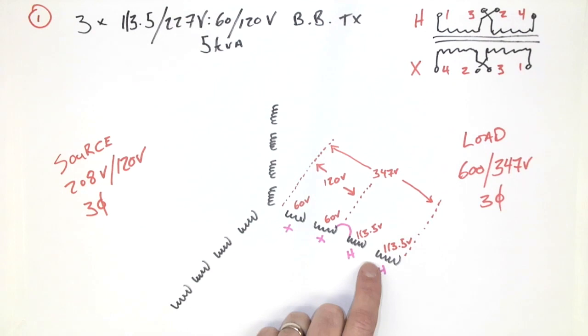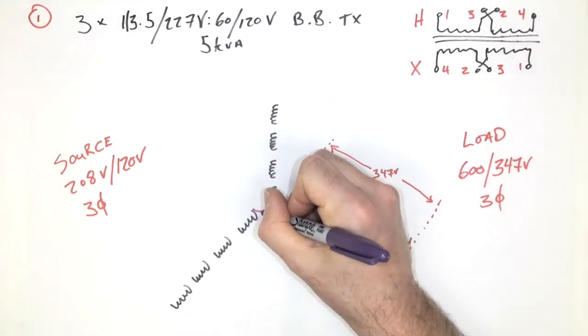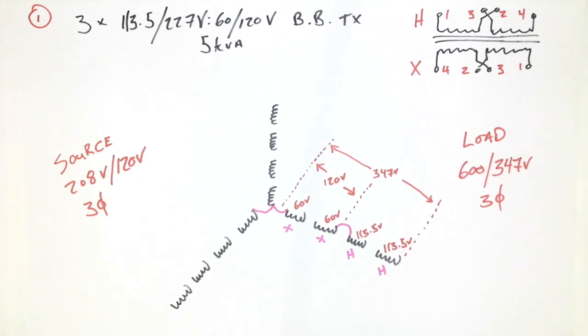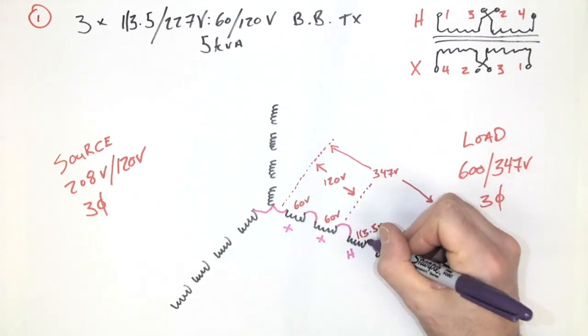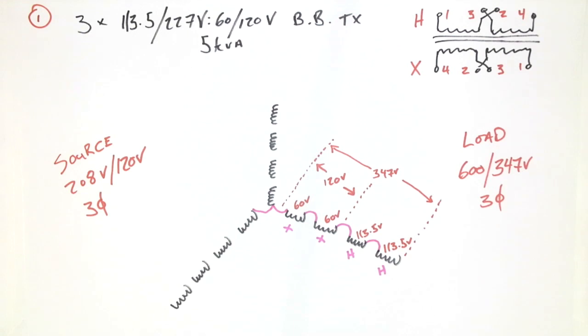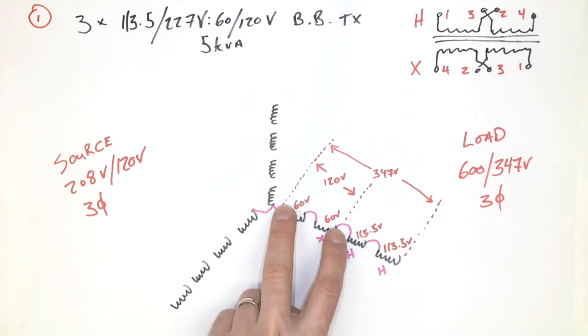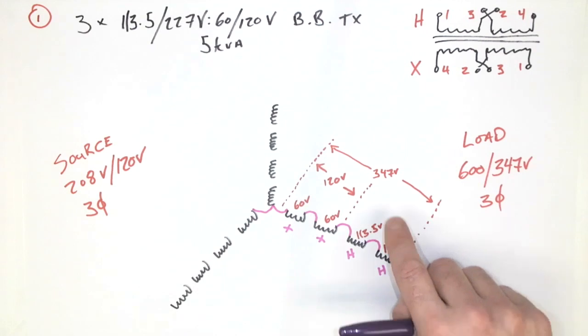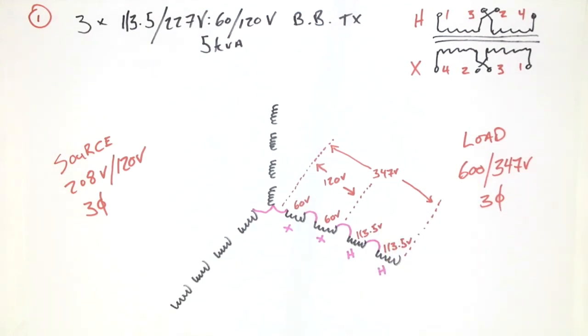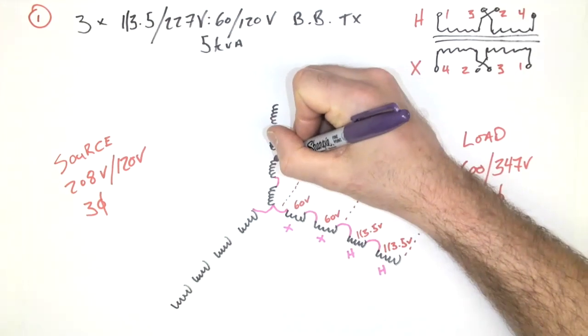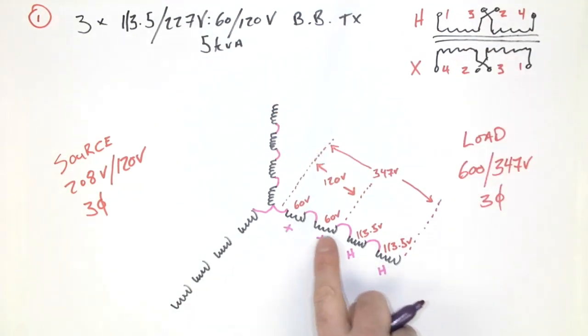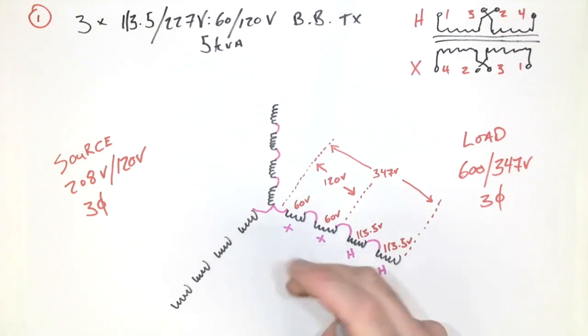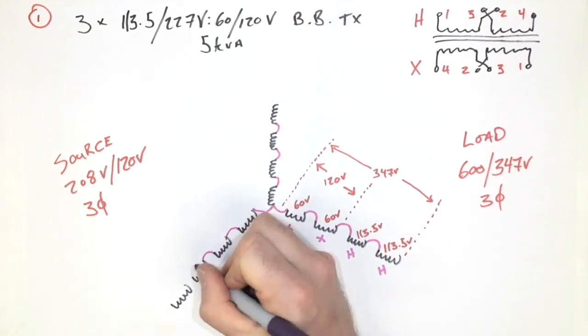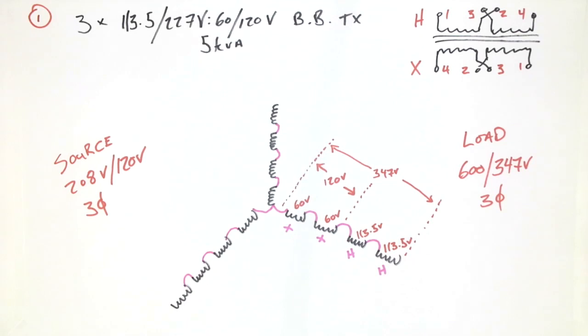120 plus 227 gives me 347. And so what this tells me is that I have a star connection here and then a series connection for all of my other windings. And that's because 120 volts plus 227 equals 347 volts. So let's do that connection on every one of these windings. This is transformer 1, transformer 2, transformer 3. Once I've got them all located, now I can start looking at the actual connections.